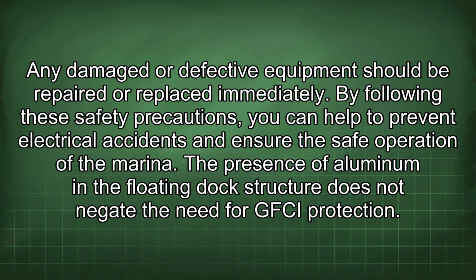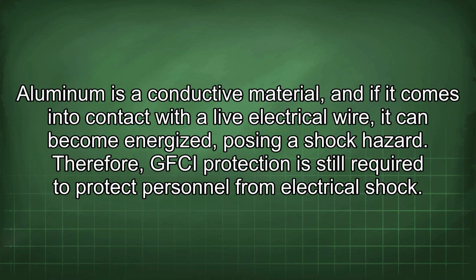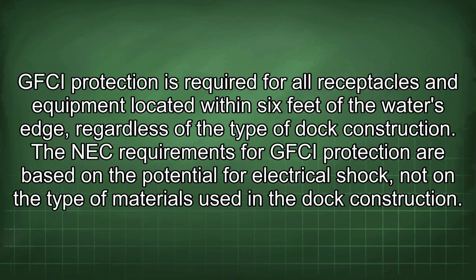The presence of aluminum in the floating dock structure does not negate the need for GFCI protection. Aluminum is a conductive material, and if it comes into contact with a live electrical wire, it can become energized, posing a shock hazard. Therefore, GFCI protection is still required to protect personnel from electrical shock. GFCI protection is required for all receptacles and equipment located within 6 feet of the water's edge, regardless of the type of dock construction. The NEC requirements for GFCI protection are based on the potential for electrical shock, not on the type of materials used in the dock construction.